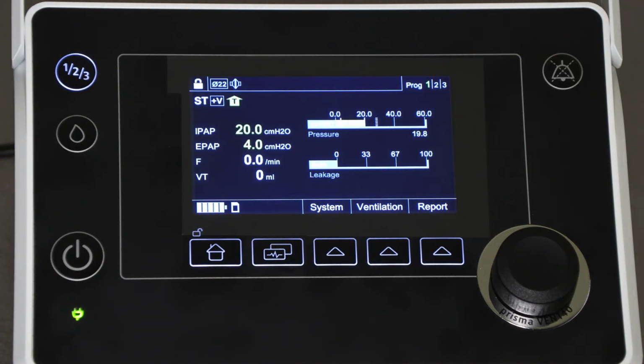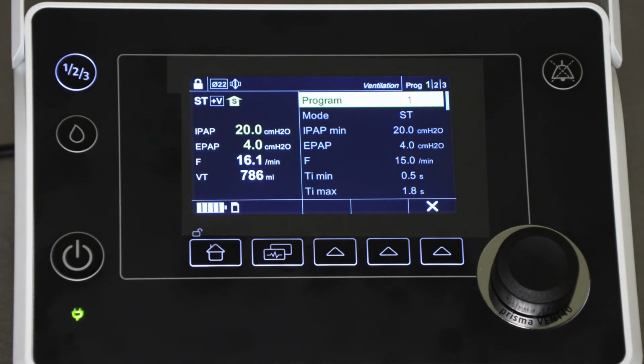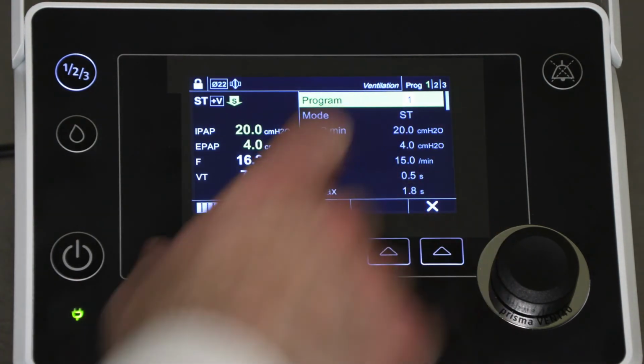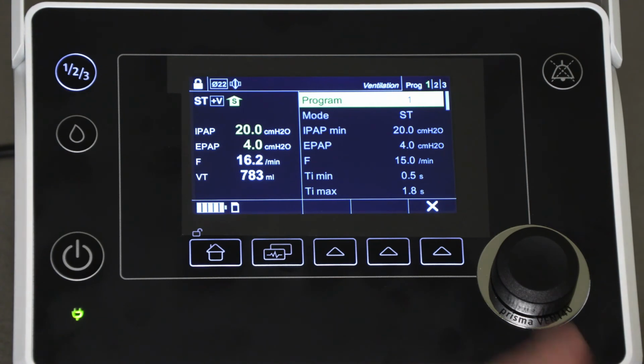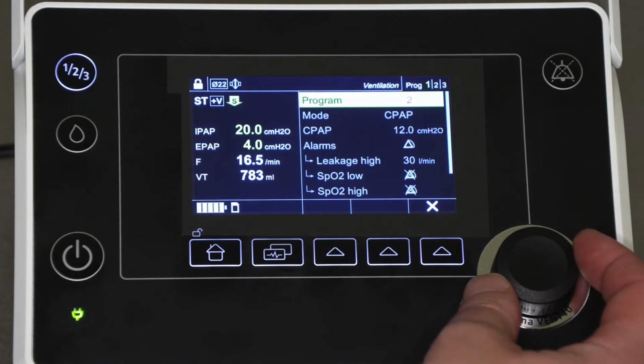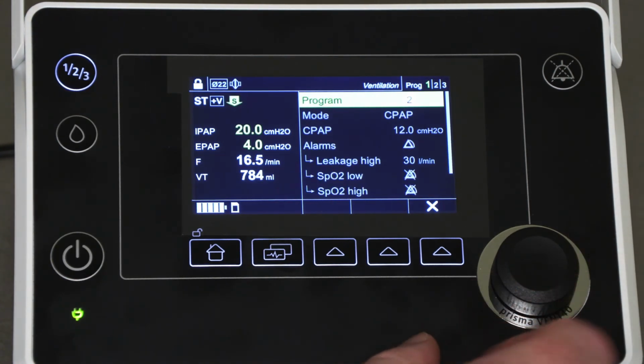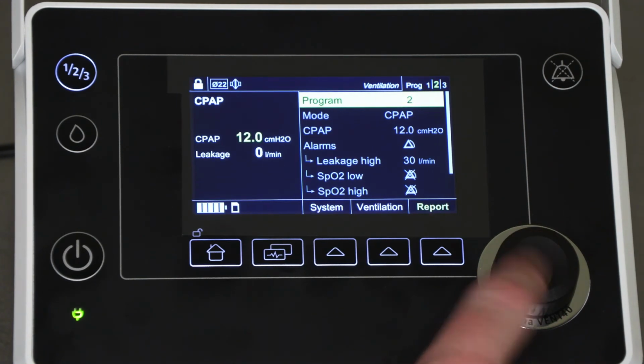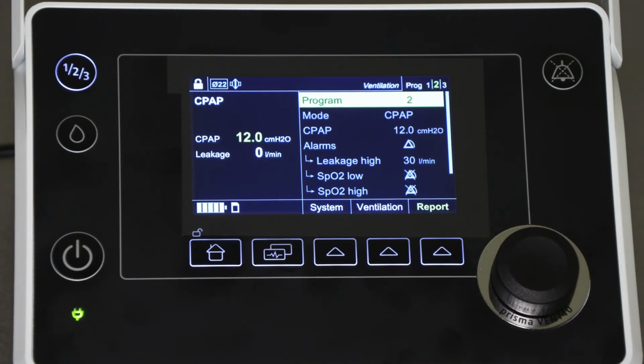But let's say this ventilator is being used by someone who uses ST mode during the day and CPAP mode at night. We've already got ventilation program 2 set to CPAP mode at a pressure of 12 centimeters. Press the program button. The ventilation program is highlighted at the top of the screen. Turn the rotary knob to change to program 2, currently CPAP mode, and press to confirm. The ventilator is now set to program 2.